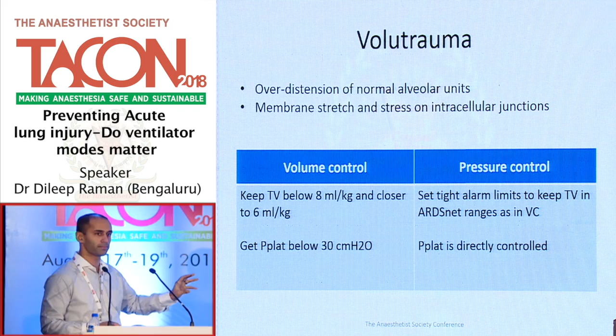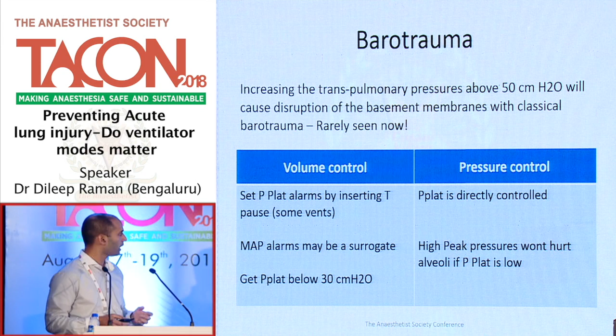So barotrauma, interestingly, was defined as a very high pressure, around 50, which we rarely use nowadays. And you hardly see it anymore in modern ventilators, because that degree of pressure-related damage to the alveolus doesn't happen. I have a picture to get that point across fairly clearly. In volume control, you can set the pressure limits to achieve that, and we'll talk about how you can get a plateau pressure alarm to kick in. And in pressure control, since you're controlling pressure directly, it's self-explanatory.